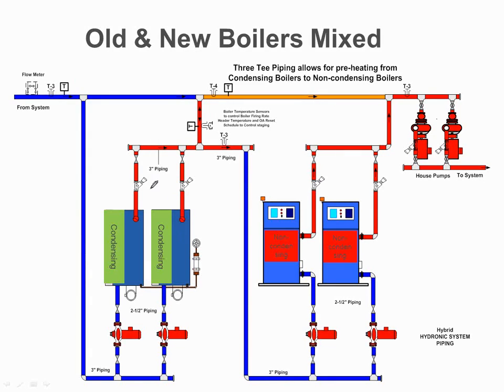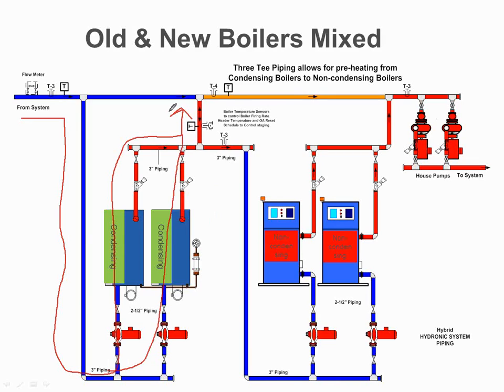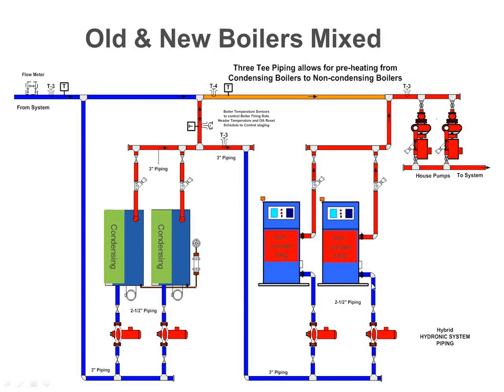Here's another system showing pretty much similar technology. You come from the system. First thing you do is you hit your condensing boilers. If it's sufficient, it just goes right to the system. It doesn't go into the non-condensing boilers. If that temperature at T3 there is not correct or still too low, then it will go over to the non-condensing boilers to raise it up to get to the proper temperature for that day and out to the system. So a little bit of piping, a little bit of controls, and there's a lot of things you can do with these. You don't have to get into an all or nothing routine with condensing boilers. This is very popular with churches and schools.